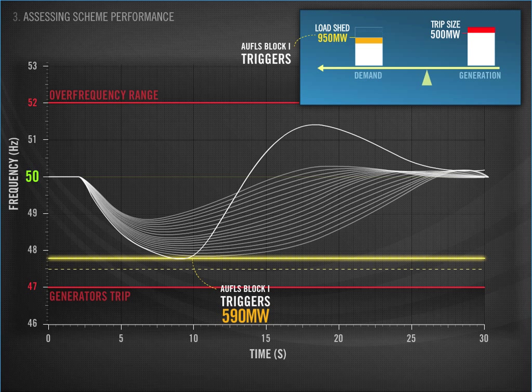In other words, it's not one for one. As you can see from this seesaw, we are shedding quite a bit more than the system needs, which results in something we call frequency overshoot. In this case, the frequency rises above 50 Hz and is heading up towards 52 Hz before it's pulled back down, and that's the result of disconnecting too much demand from the system.